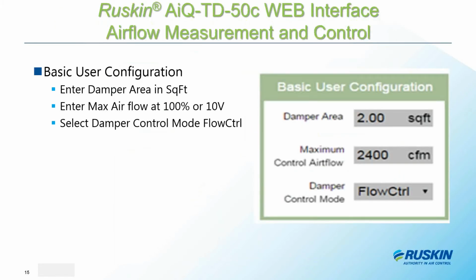So the things that have to be configured is the square footage of the damper that we're dealing with. So, for example, if you had a 2 square foot damper, you would put in 2 square feet, and if the maximum airflow that you anticipated seeing from the unit was 2400 CFM, you'd put in 2400 CFM, and then you would toggle it to flow control.